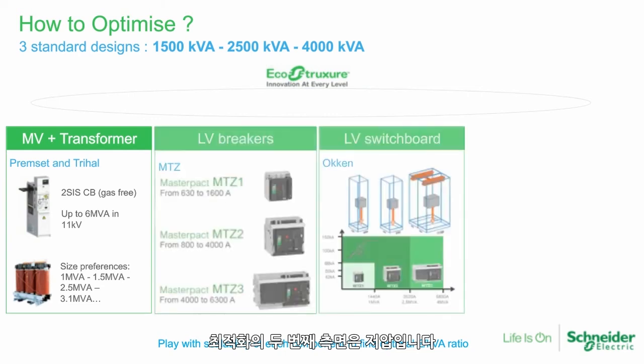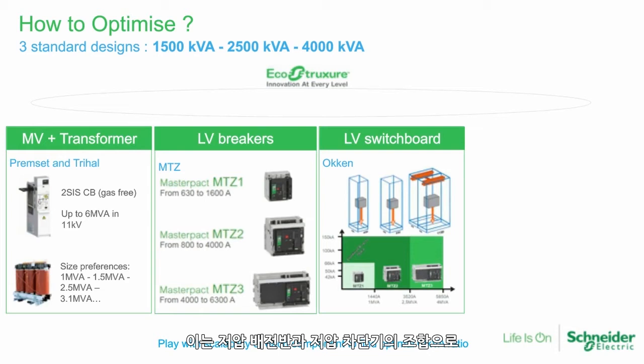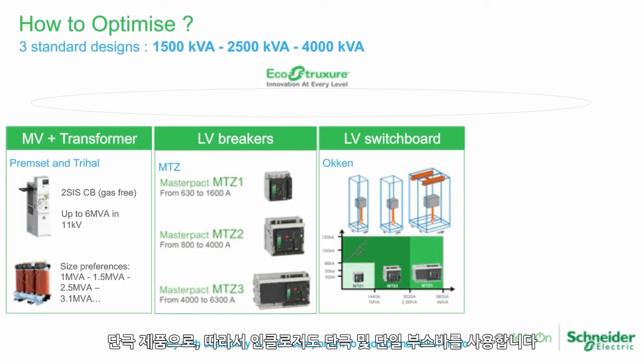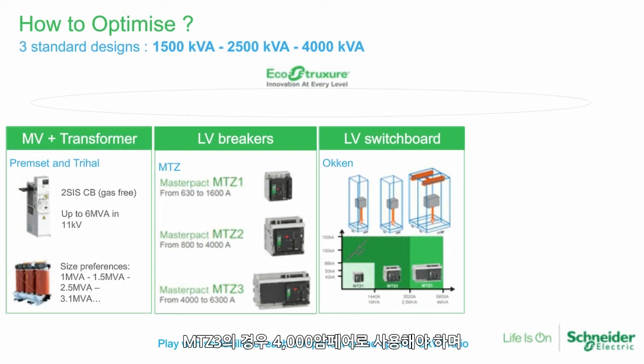The second aspect of the optimization is about the low voltage. It's a combination of the low voltage switchboard with the low voltage breakers. As you can notice, the first and the second MTZ we are using from the Schneider portfolio is a single pole. So meaning that in terms of enclosure, we will have also single pole, single bus bar, and the MTZ3 that we have to use for the 4000 amps is a dual pole and a dual bus bar in the enclosure. So there is a big chance that, at least for the main breaker, the incomer breaker that protects the overall switchboard, we think that this breaker is not necessarily the most cost-effective, and in terms of footprint is not necessarily the smallest, even if the power that we can use is higher.